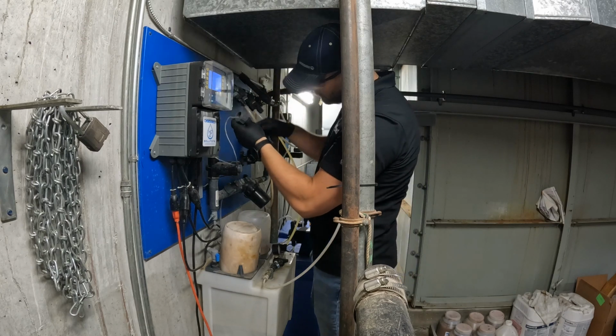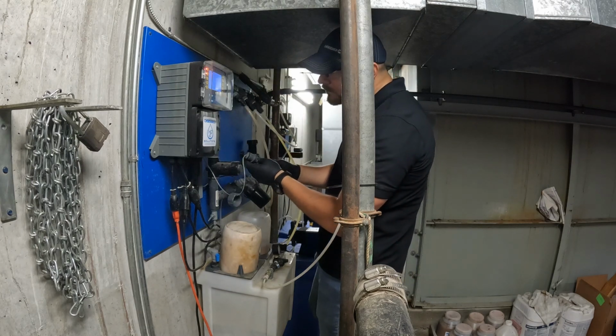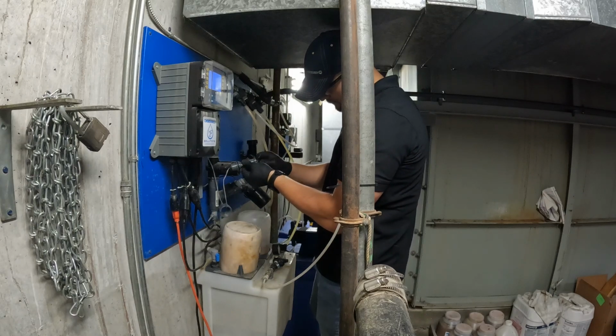On every visit, you should ensure the flow sensor is clean of debris. You can test that it is working by simply sliding it up to make contact and see if the controller responds.